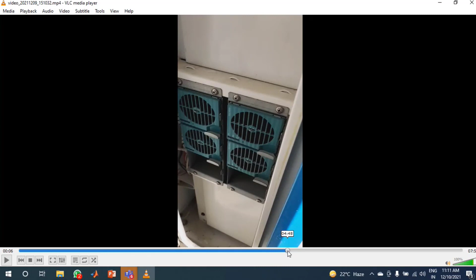These SMPS are of modular type. There are 6 SMPS, each of 3 kilowatt. They are modular because if we use only one SMPS and any problem occurs, the entire system would be under faulty condition. With modular SMPS, if any one unit is faulty, you can just replace that SMPS and continue your system.